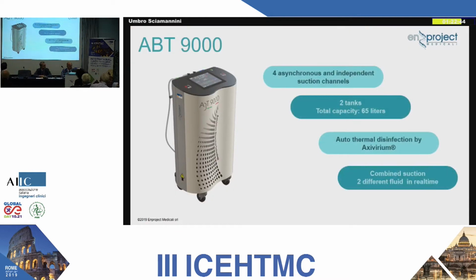The ABT 9000 is the bigger one, with 4 independent asynchronous suction channels, 2 tanks for a total of 65 liters of liquid, and autothermal disinfection with Axivirium product. It's autothermal because inside the device there is a heater that provides 40 degrees of temperature for the best possible disinfection. With 2 tanks we can treat 2 different products at the same time — in real time we can treat biological fluid, and also treat ultrafiltrate dialysis liquid from dialysis rooms.